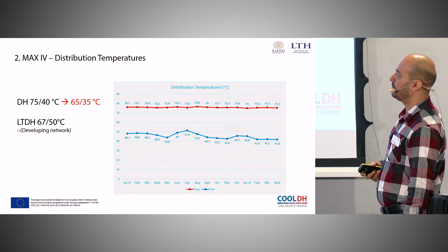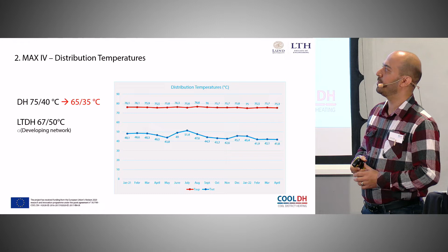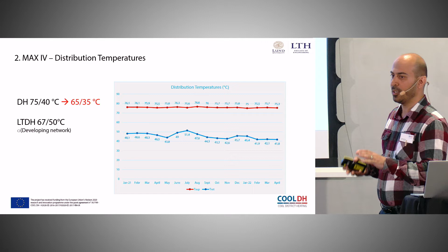40-45. But in the future, by developing the low temperature network, it's planned to decrease the supply temperature from 75 to 67. And also, there is a heat exchanger inside of the MAX IV to reduce the temperature from 75 to 67 to provide the low temperature network. That is a small part of the heating.